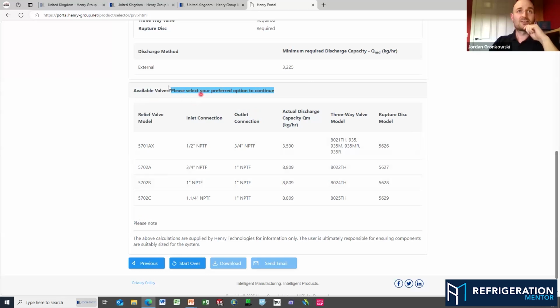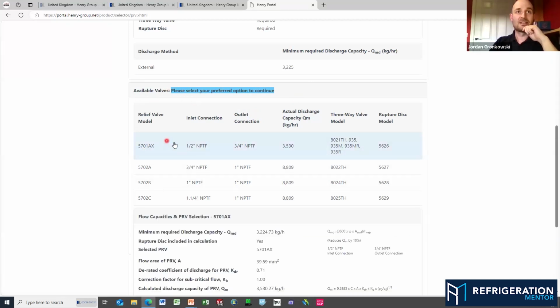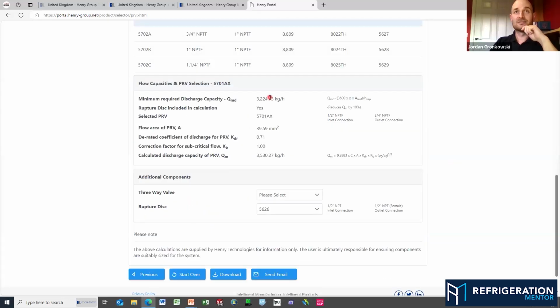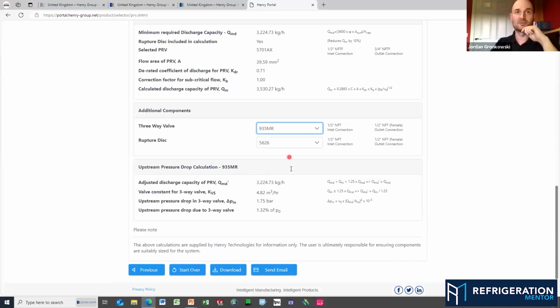Okay, so last point is just to, as it says here, connect which one you want. So let's go for the 5701AX. Once we click that box, we get more data at the bottom here. Again, here's your formulas that we talked about. Here's all the different parameters of the valve that's come out. Again, we've got the option here to select which three-way valve we want. Just pick that up at the moment. It'll give you some more parameters of the three-way valve, which is important when you look at pressure drop, which I'll do in a second.